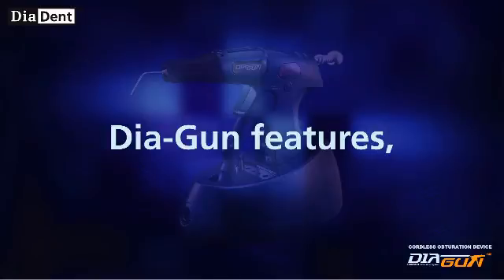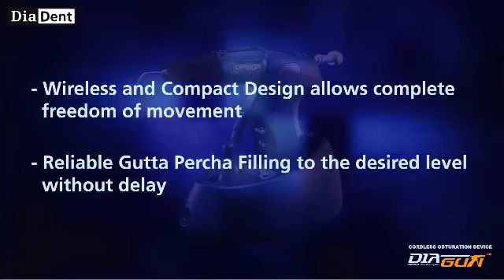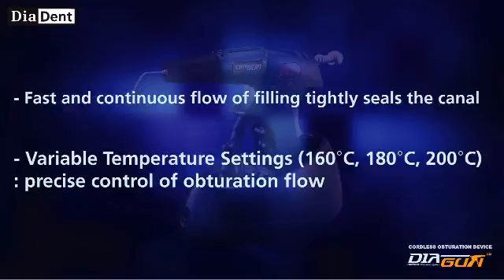Dia-Gun features a wireless and compact design that allows complete freedom of movement. Reliable Gutta Percha filling to the desired level without delay. Fast and continuous flow of filling tightly seals the canal. Variable temperature settings — 160 degrees Celsius, 180 degrees Celsius, and 200 degrees Celsius — allow precise control of obturation flow.